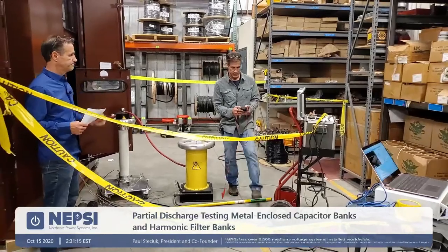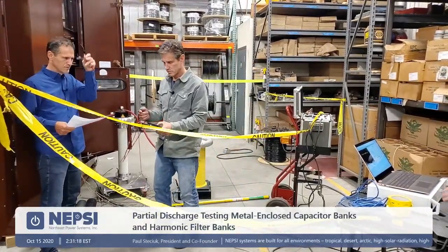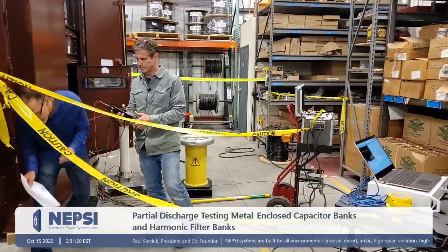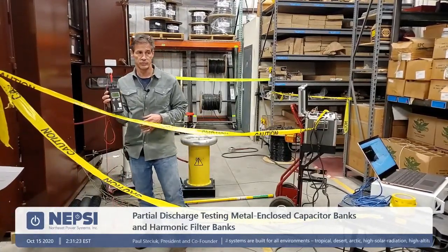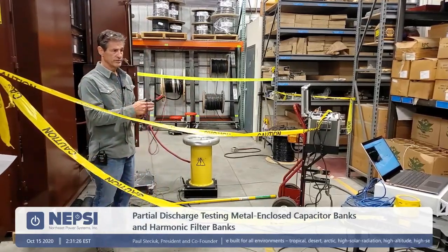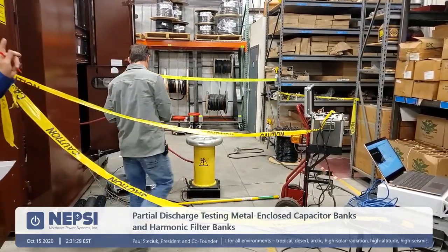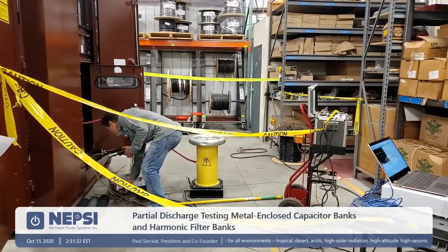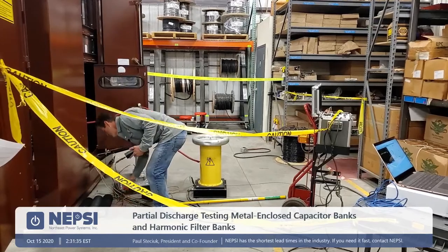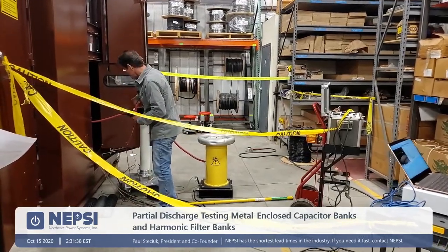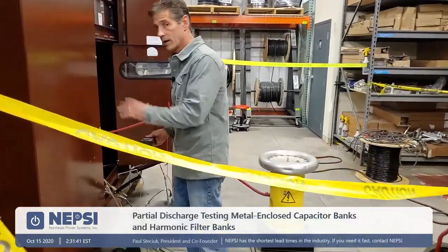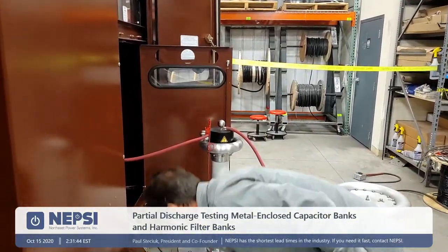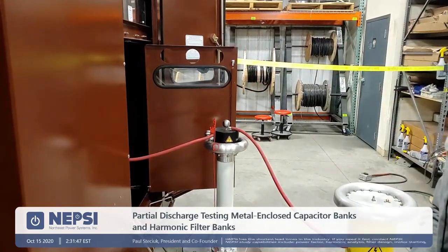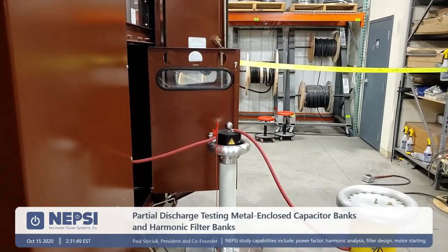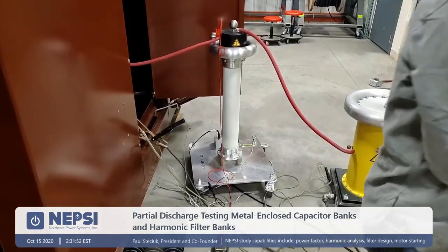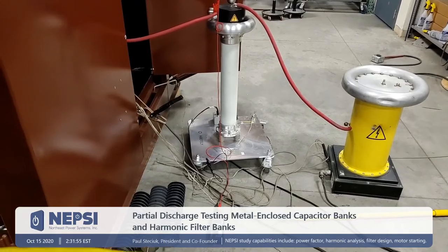All right, so this is just a calibration device for the partial discharge test. We set 100 picocoulomb. So we're going to calibrate this instrumentation with this device to 100 picocoulomb. We do that, attach one side to ground, attach the other side to the output. We're putting 100 picocoulomb of noise basically onto the A phase bus. And then we found that we actually need to step away from it a little bit so we don't generate noise. And now you come over to here, Jessica. And Jessica can explain a little bit what she is doing.